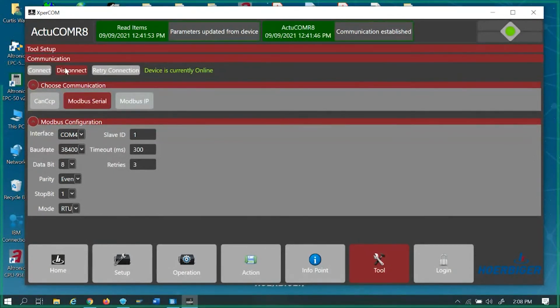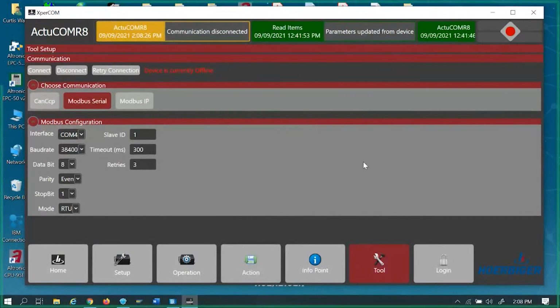I'll disconnect from it here. So basically, when you hook up to this, a lot of times this interface number is going to be different. You need to find out what port your device is hooked up to on your RS-232/485. Typically, mine's always on 4, so that's the one I use. Do not mess with any of this baud rate, parities, or anything like this, or even the slaves.